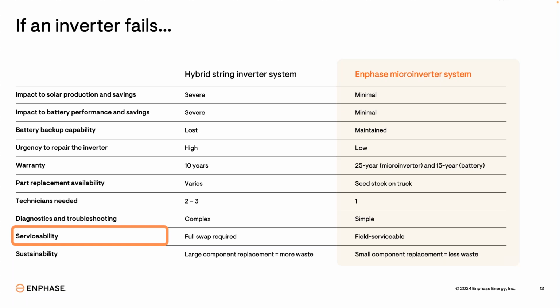Microinverters on the solar array or battery can be replaced on site. Today's hybrid string inverters normally can't be serviced on site, and the entire heavy unit must be shipped back to the manufacturer, meaning significantly more downtime and loss of bill savings for the homeowner.